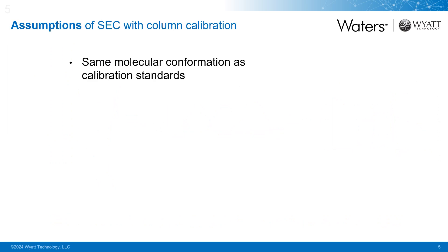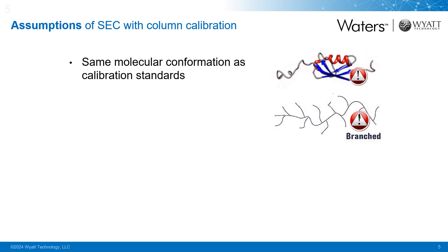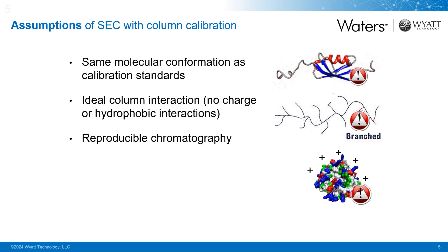SEC alone requires some assumptions to determine your molar mass. One has to assume that our sample has the same conformation as the column calibration standards, and therefore will have the same relationship between size and molecular weight. For example, when you calibrate using a globular protein, we're assuming that our sample is also an unmodified globular protein. When we calibrate with a linear polymer, we're also assuming that our polymer has no branching of any kind. And since SEC elution is based on hydrodynamic volume and not molecular weight, if our molecule has a different conformation than those standards, it will have a different relationship between molar mass and size compared to the column calibration curve, leading to incorrect conclusions about your sample's molar mass.